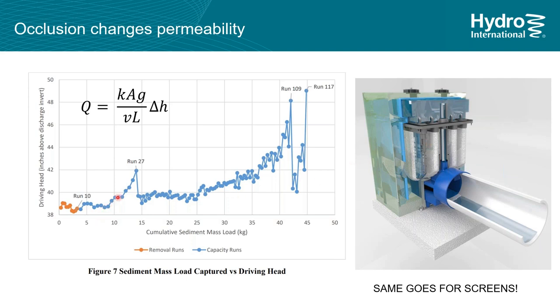And so in this case, we were running the test at a certain concentration, and we realized, oh, we need more backwashes. So we went back down to the minimum concentration that the test protocol allows, which is around 200 milligrams per liter, a real typical concentration for stormwater. And you can see that the backwash just keeps that filter chugging right along. And it's not until you get here that the occlusion starts catching up with it. And we're able to almost triple the amount of sediment that can be captured by this product. So this product is called the extended maintenance cartridge, the EMC version of the upflow filter, and it's to help keep filter hydraulics under control.